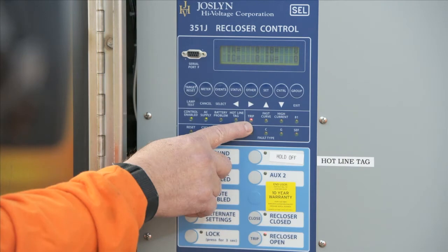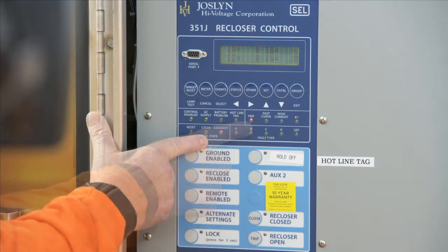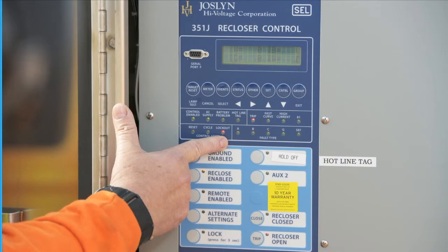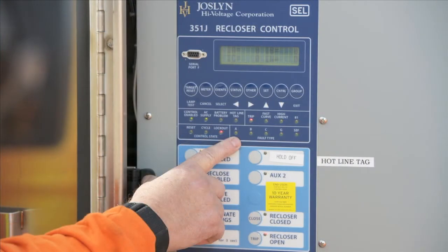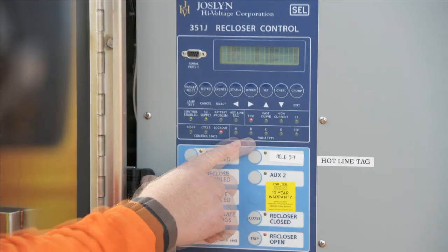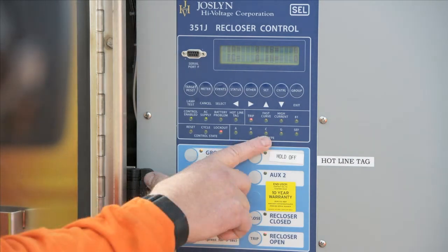Auto reclosing. The SEL 351 can auto reclose a circuit breaker up to 4 times before lockout. One can use the SEL logic control equations to program the SEL 351A to perform the reclosing functions. The recloser shot counter controls which protective elements are involved in each reclose interval. Applications include fuse and trip saving schemes. The front panel LEDs Reset, Cycle, and Lockout track the recloser state.